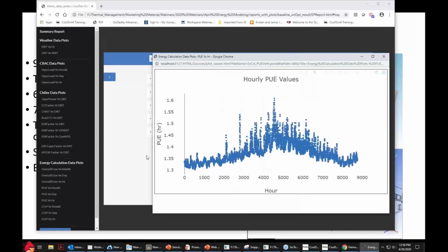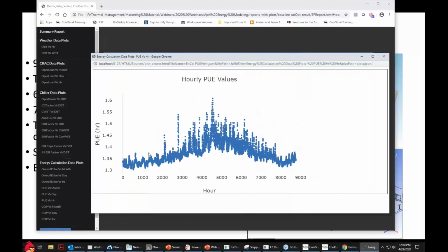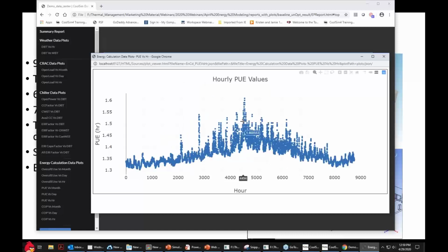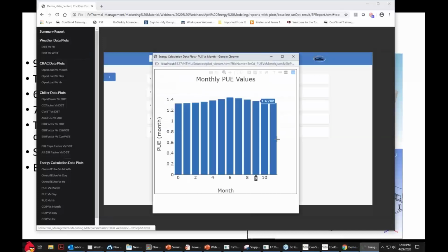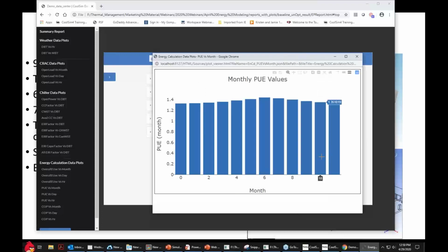This is part of the issue with PUE that you and I have talked about, and I pointed out early on, that PUE needs to be over a period of time, and you can see why. And now if you go to the monthly, you'll see that it doesn't get up to 1.6. There's very little variation when you average it on a month-by-month basis. The variation exists within the hours or the days.